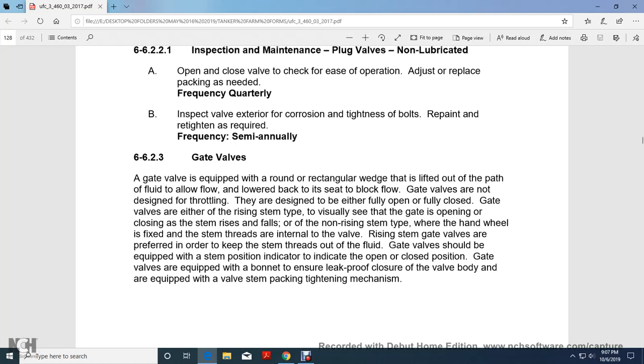Gate valves are either of the rising stem type, where you can visually see if the gate is opening and closing as the stem rises and falls, or the non-rising stem type, where the hand wheel turns but the stem threads are internal to the valve. Rising stem gate valves are preferred in order to keep the stem threads out of the fluid. Gate valves should be equipped with a stem position indicator to indicate the open and closed position.